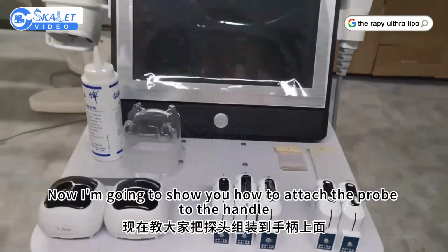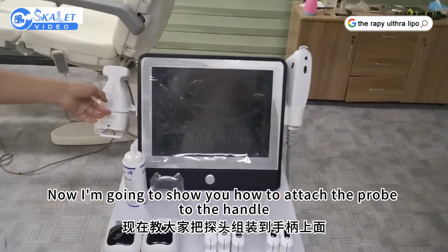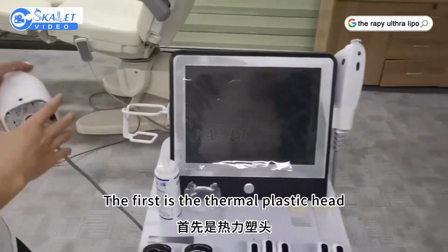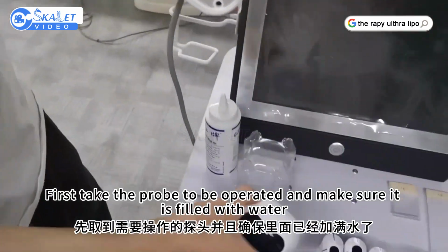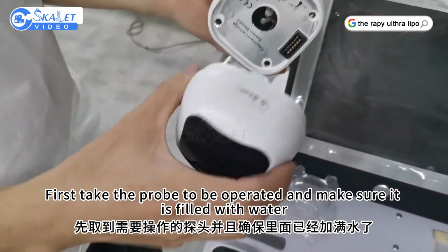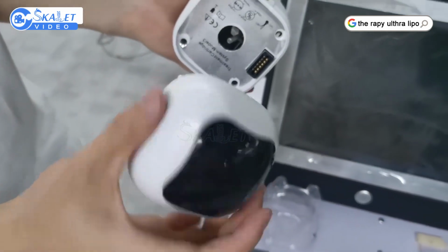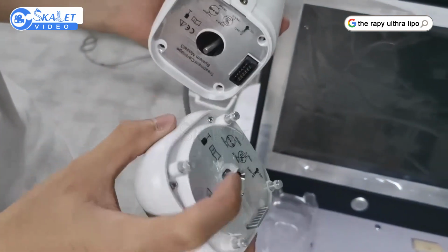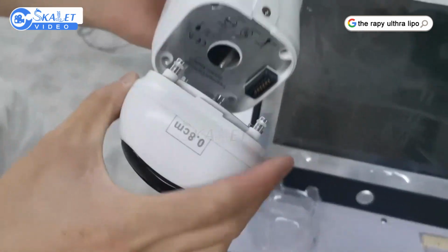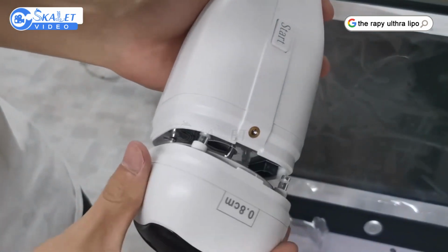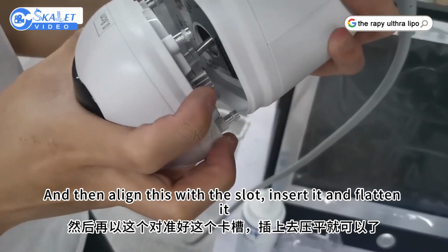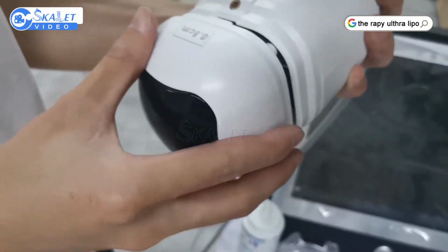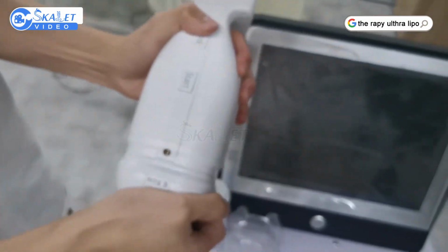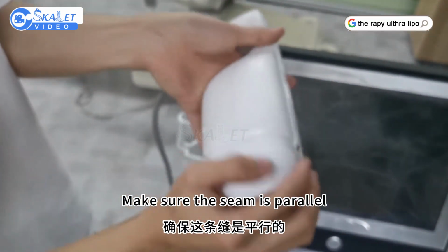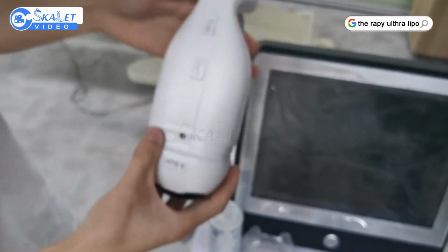Now I'm going to show you how to attach the probe to the handle. The first is the thermoplastic head. First, take the probe to be operated and make sure it is filled with water. Align this in the middle with this. So align these two. And then align this with the slot. Insert it and flatten it. Make sure the seam is parallel. The handle is now installed.